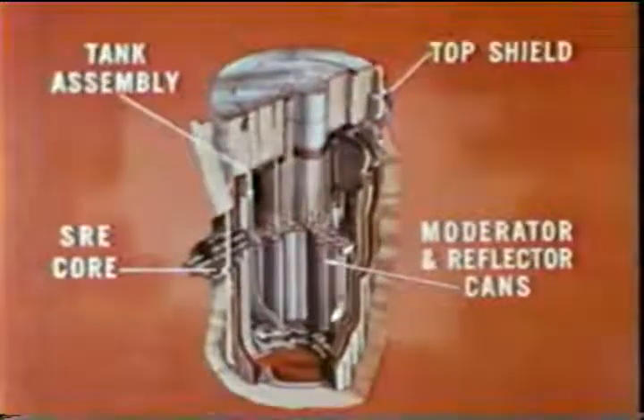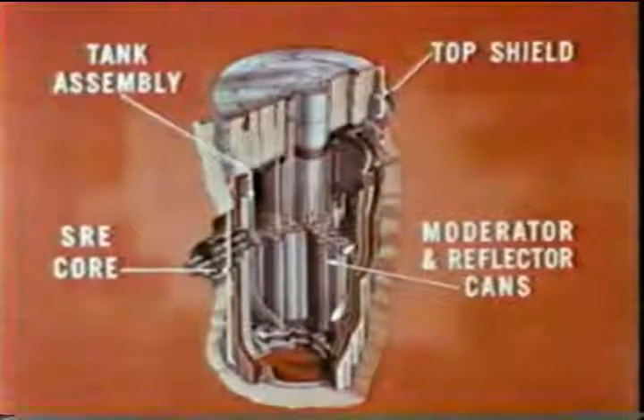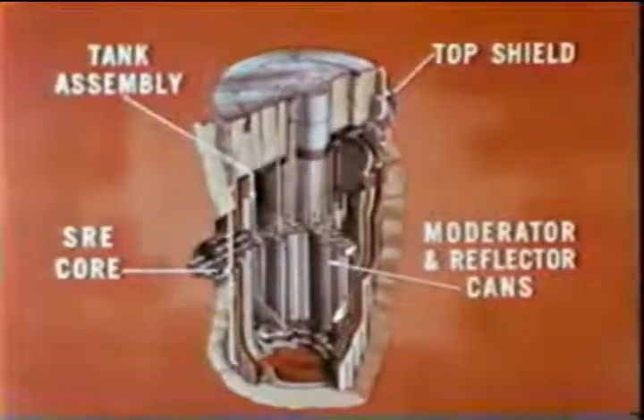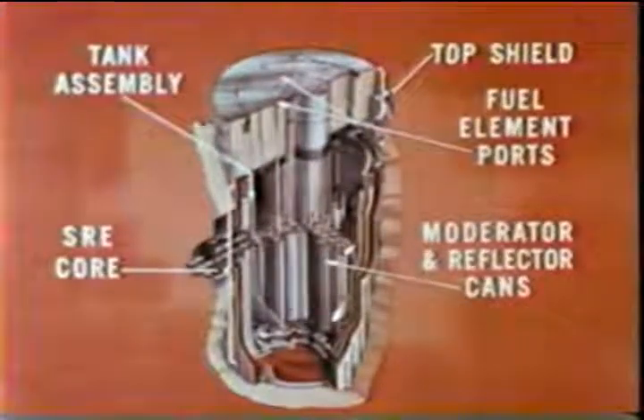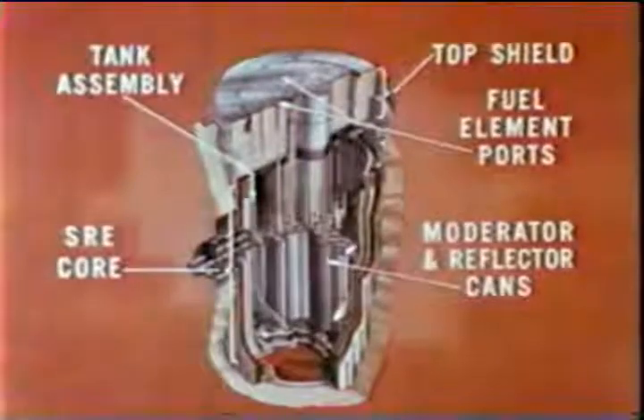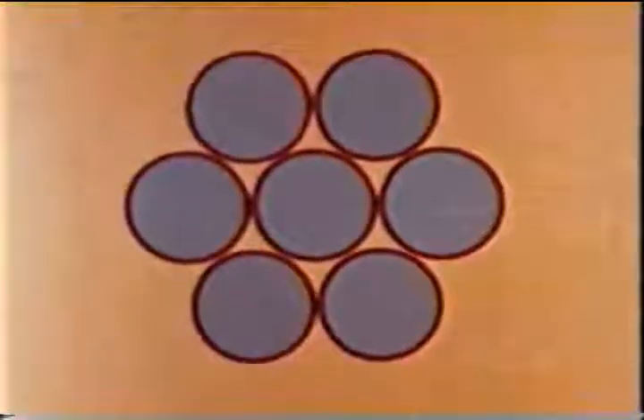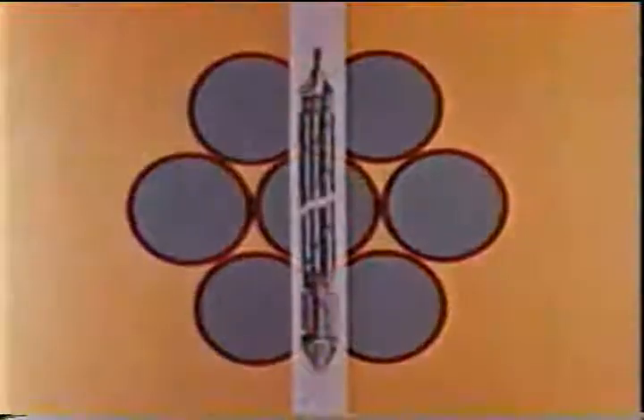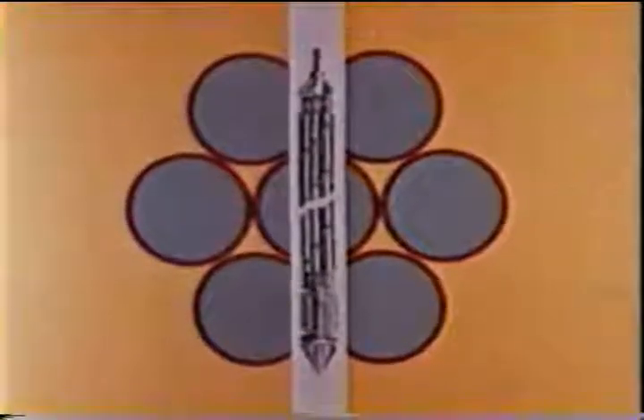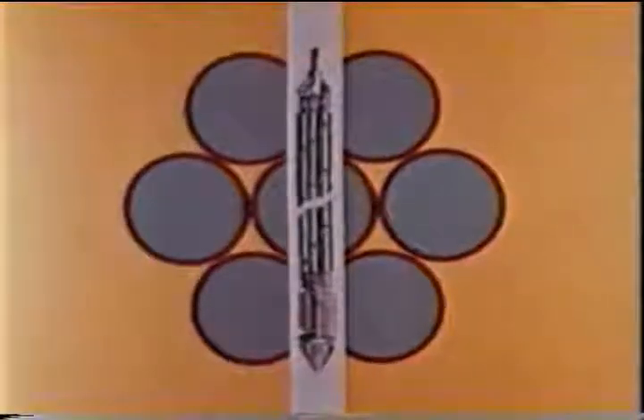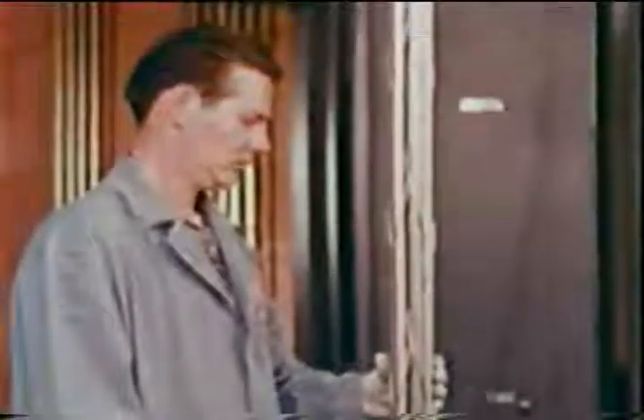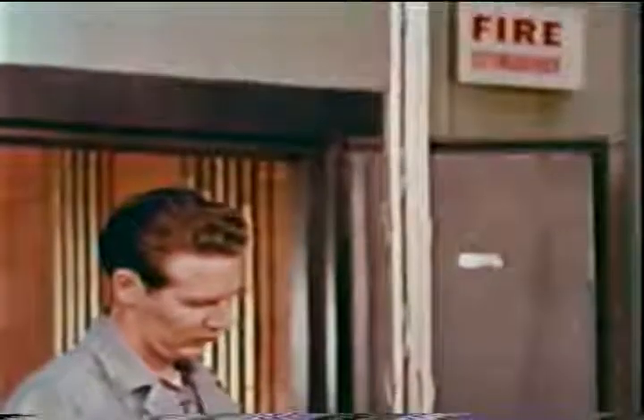Moderator and reflector cans, 10 feet in height, comprise the stationary portion of the reactor core. Initially, 43 fuel elements were suspended within the reactor core from the top shield. The first reactor fuel elements contained 7 uranium fuel rods, approximately 8 feet long, arranged in a cluster. The rods, which were each 3/4 of an inch in diameter, were clad with stainless steel and separated from each other by stainless steel wire wrap. NaK, an alloy of sodium and potassium, was used in the rods as a thermal bond. NaK is compatible with the sodium and other materials in the SRE.